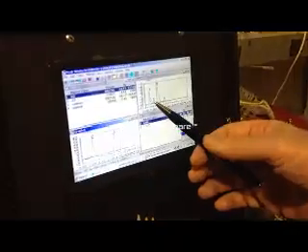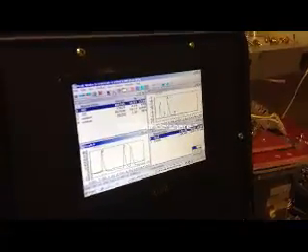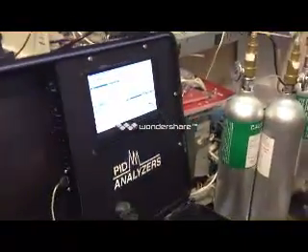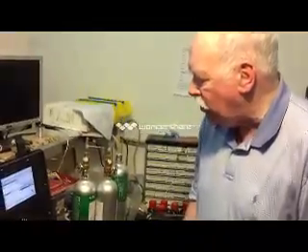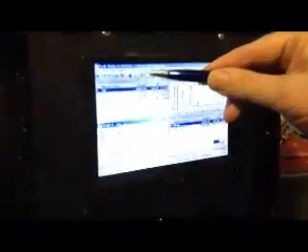Now what we're doing is a valve switching here so that we don't interfere with the analysis, so we can basically send some of the sample to flush it to air, and then it doesn't get onto the column. And this is one where we have two parallel columns in the GC.